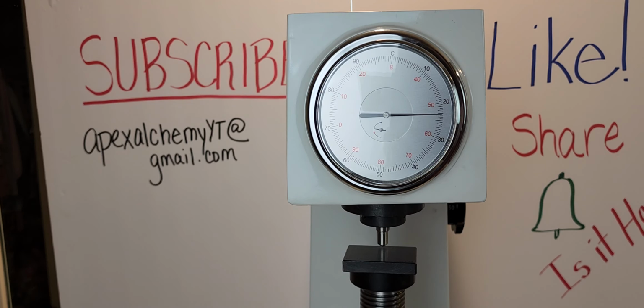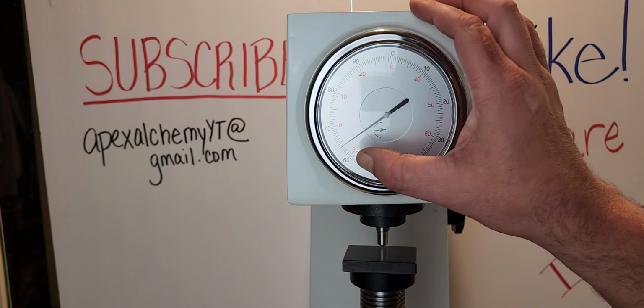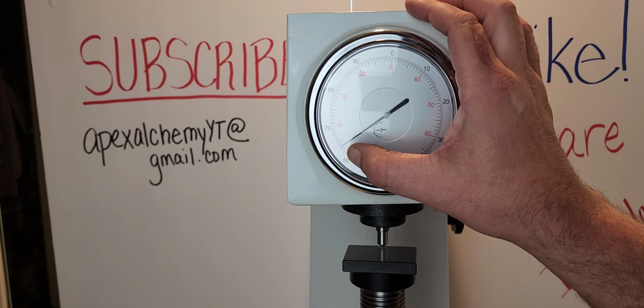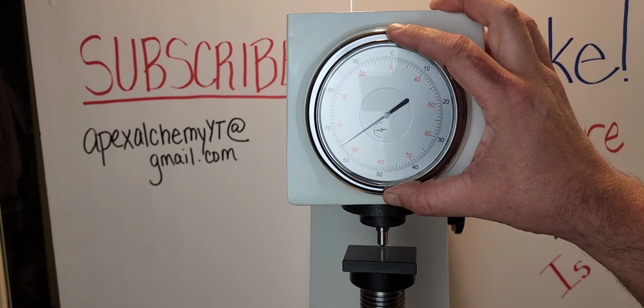And as always, we're looking for the number 63. That is our magic number. 63 is the Rockwell hardness of that test block. Our room is set up at 70 degrees, temperature controlled, which is critical for this machine to operate properly. Even the knife blades need to be 70 degrees, all that stuff as well. And we're actually, yeah, it's like 63 and a quarter.